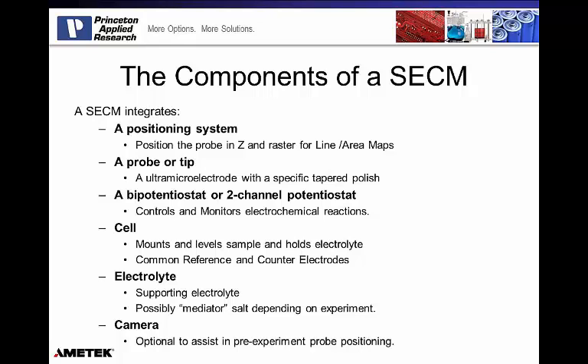Then we have a probe, or often you'll see in the literature it called a tip. In an SECM, this is typically an ultramicroelectrode with a specific tapered polish. We're going to talk a little bit about what that polish is and why it's important. It's crucial in doing approach curve type work. But it's typically an ultramicroelectrode, and for us with a physical electrochemistry background, it's an ultramicroelectrode disc, and it's a very well characterized type of response.